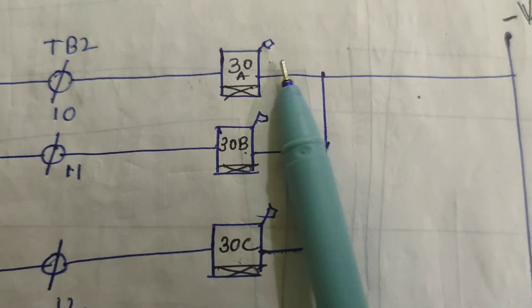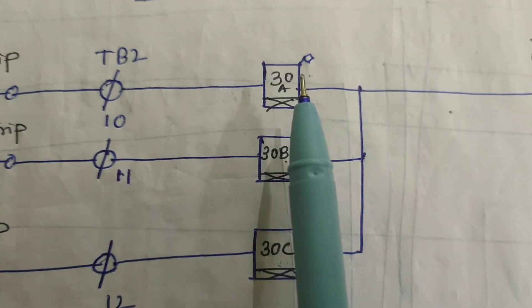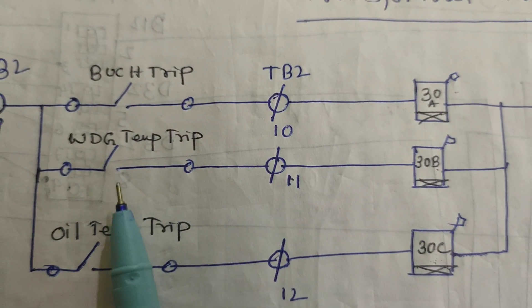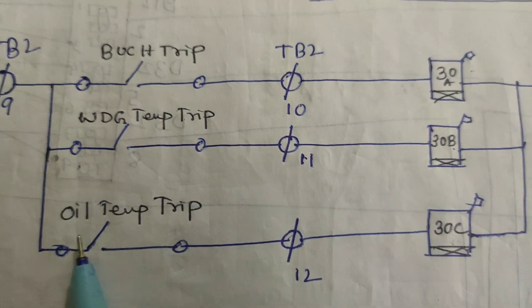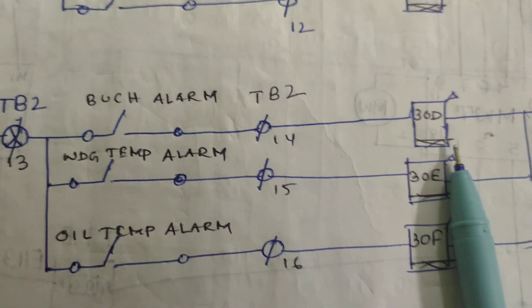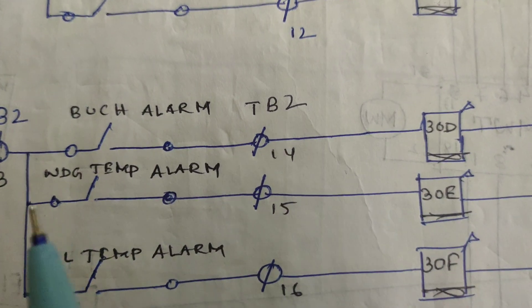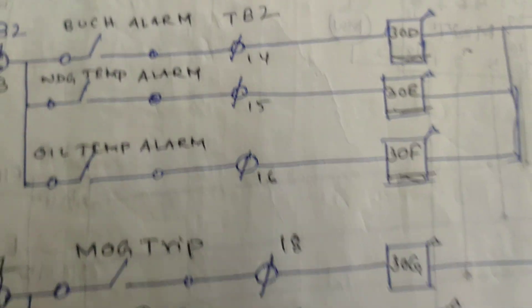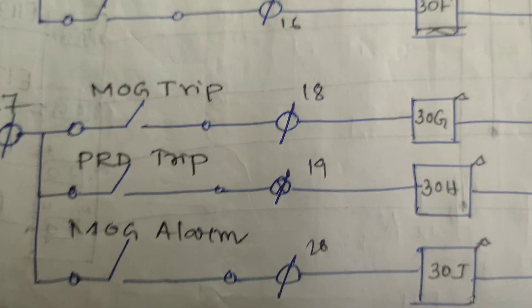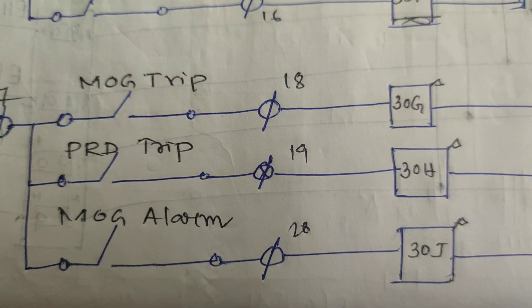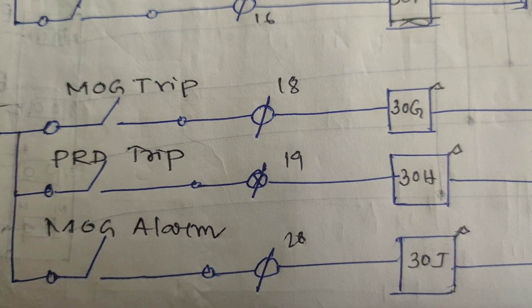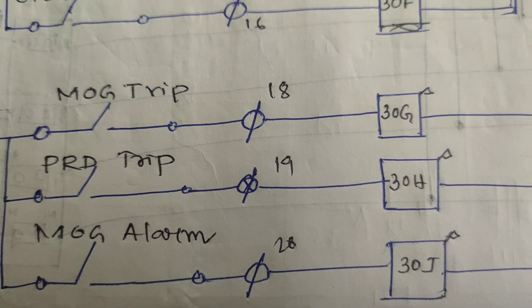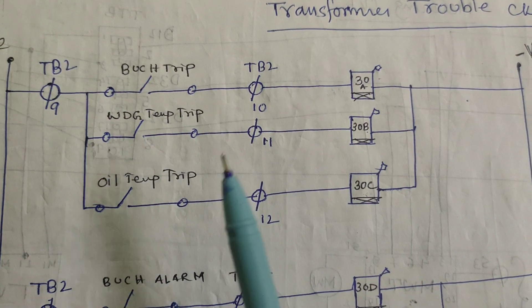30A is the Buchholz trip flag relay. 30B is the winding temperature trip relay. 30D is the Buchholz alarm. 30E is the winding temperature alarm. 30F is the oil temperature alarm. 30G is the MOG trip relay. 30H is connected for the PRD trip. 30J is for the MOG alarm.